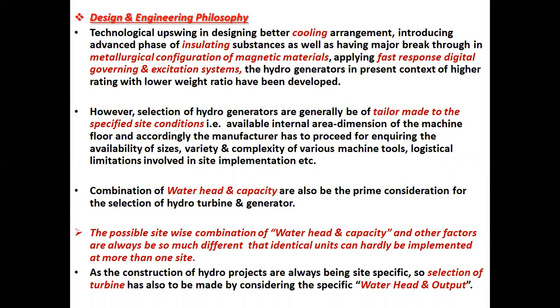However, selection of hydrogenerators is generally tailor-made to the specified site conditions, that is, the available internal area dimension of the machine floor, and accordingly the manufacturer has to inquire about the availability of sizes, variety, and complexity of various machine tools, logistical limitations involved in site implementation, etc. Combination of water head and capacity are also the prime consideration for the selection of the hydro turbine and generator, both.